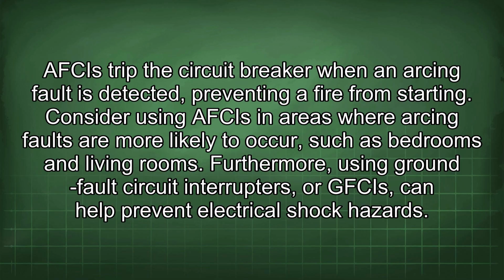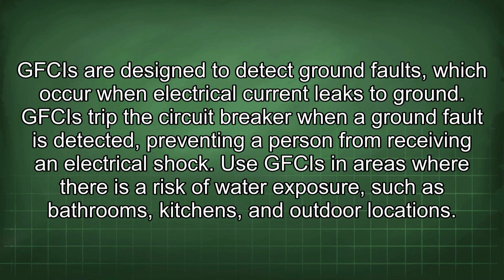Furthermore, using ground fault circuit interrupters, or GFCIs, can help prevent electrical shock hazards. GFCIs are designed to detect ground faults, which occur when electrical current leaks to ground. GFCIs trip the circuit breaker when a ground fault is detected, preventing a person from receiving an electrical shock. Use GFCIs in areas where there is a risk of water exposure, such as bathrooms, kitchens, and outdoor locations.